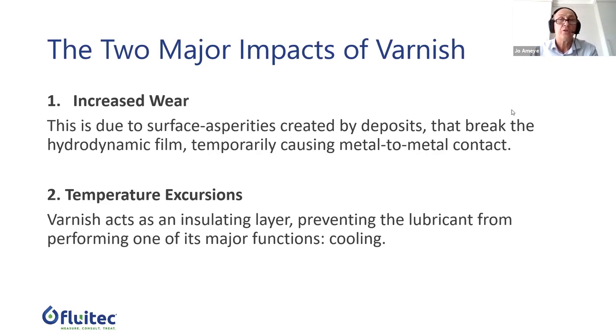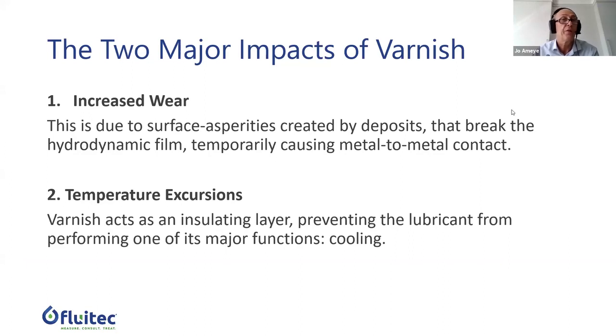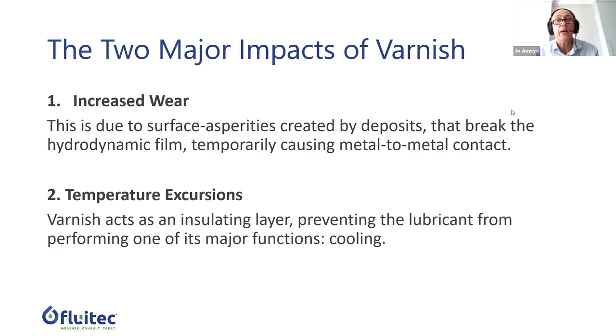The two impacts I will try to cover in this short presentation are the nexus between what you see in mechanical issues — like wear, vibration, and temperature — which are usually preceded by chemical changes. The first is the increased wear created by varnish, because surface asperities are created by these deposits. Due to the polarity of the varnish, which is attracted to the metal, the white metal is going to influence and break the hydrodynamic wedge or oil film, disrupting hydrodynamic lubrication conditions, which can cause metal-to-metal contact.